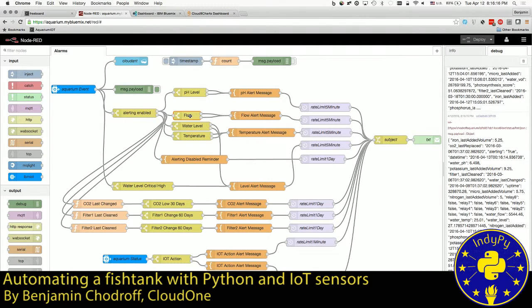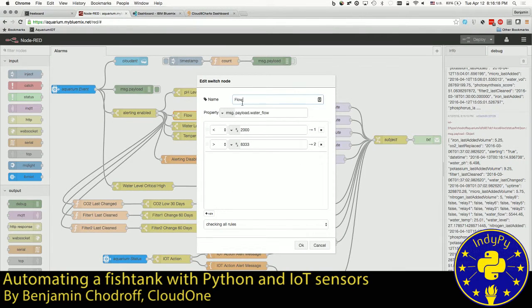For example, I want to take my flow information. So I'm going to say my property, take my message, and parse out from the JSON, from the payload, my water_flow variable. And if that number, which is an integer, is less than 2,000, send it to output 1. And if it's greater than 8,333, send it to output 2.